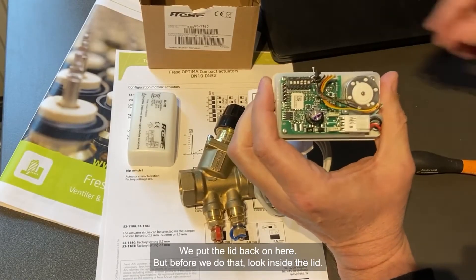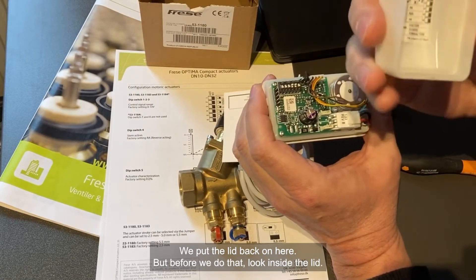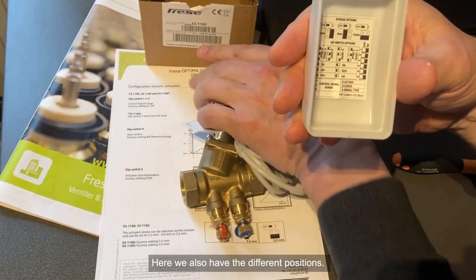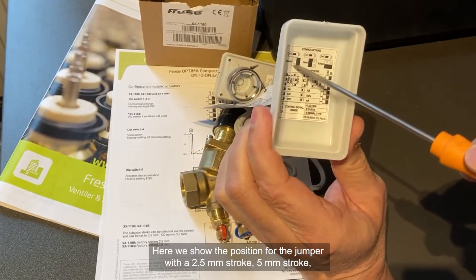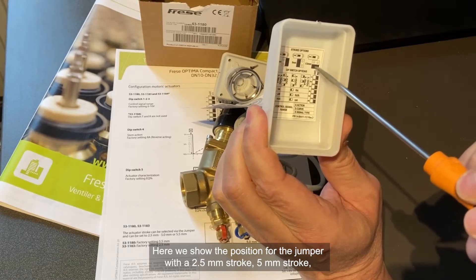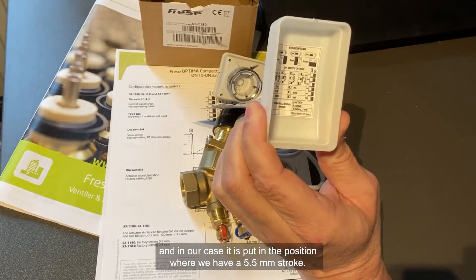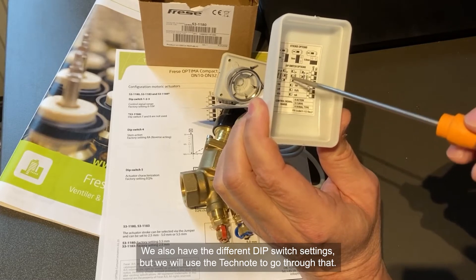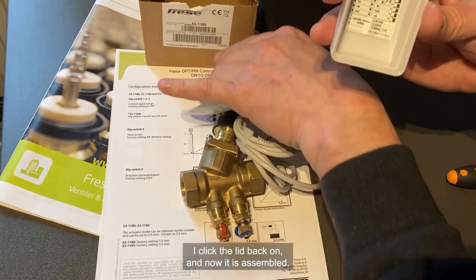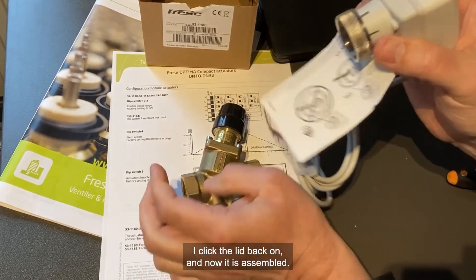We put the lid back on, but before we do that, look inside the lid. Here we have the different positions shown for the jumper: 2.5 mm stroke, 5 mm stroke, and for our case it's set to the 5.5 mm stroke position. We also have the different dip switch settings, but we will use the Technote to go through that. So I will put the lid on, click it, and now it's assembled.